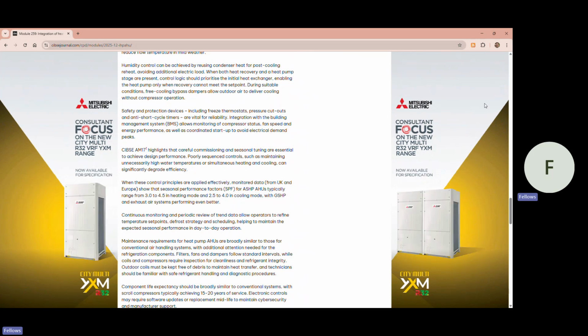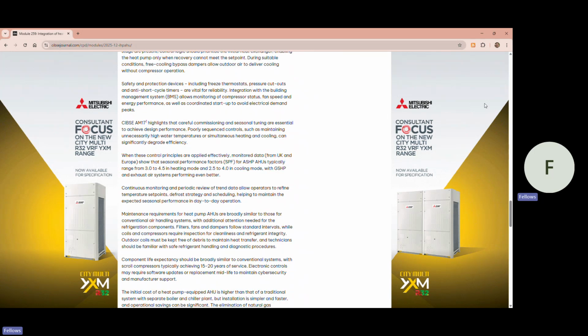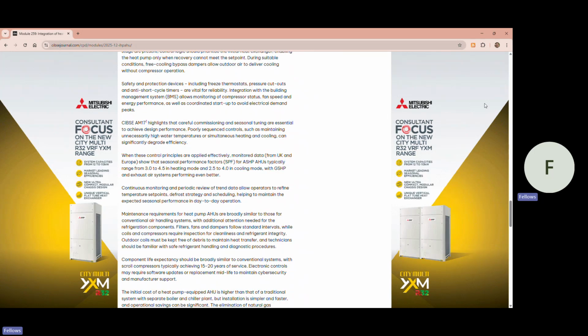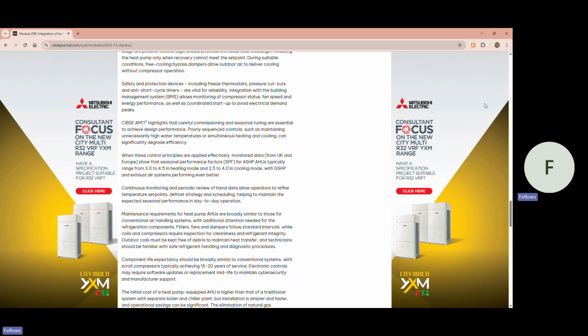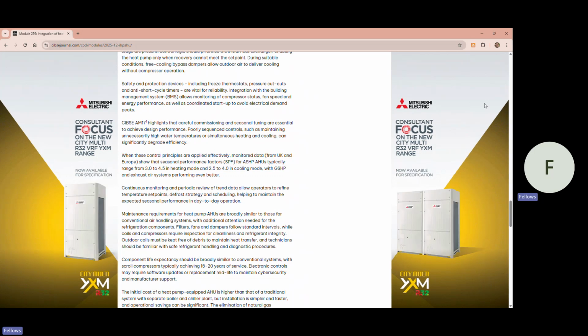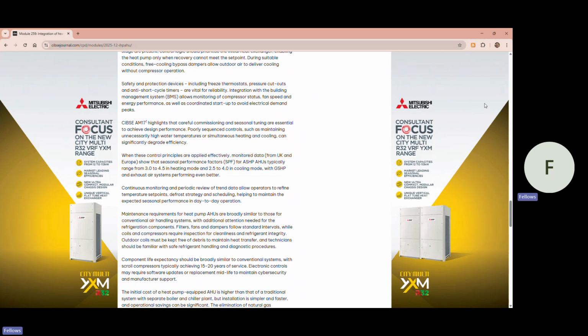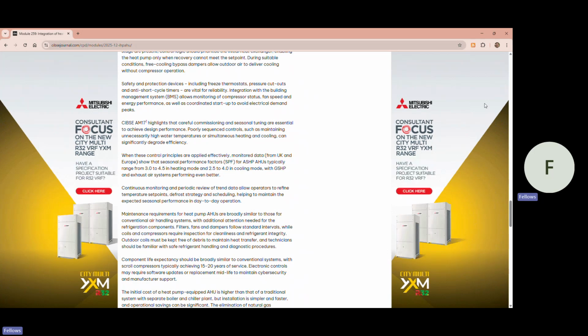When these control principles are applied effectively, monitored data from the UK and Europe shows that seasonal performance factors, or SPF, for air source heat pump AHUs typically range from 3 to 4.5 in heating mode and 2.5 to 4 in cooling mode, with ground source heat pump and exhaust air systems performing even better.